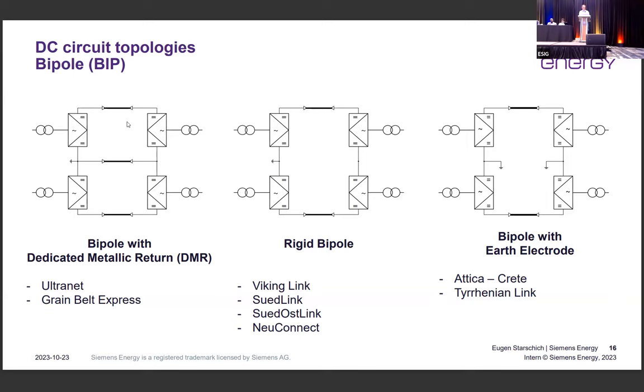The big advantage of these bipolar configurations is that in case of a converter fault or a cable fault, you can still operate with at least 50% of the transmission power. This is exactly what we want, that in a single fault we are not losing the full transmission capability. As for the third conductor, the dedicated metallic return, I would say that in the lifetime of the HVDC converter, 99% of the time it is not in operation.